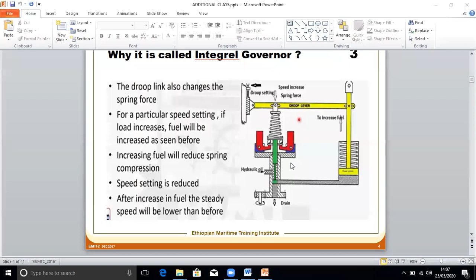You must understand why, when you increase the load, the speed reduces. This is because of this: the load current increases, and when the load current increases, the armature current will increase. So there is too much magnetic flux. The armature also produces a magnetic effect which will try to pull the rotor back. When the rotor is pulled back, the prime mover speed is dropped, and that is sensed by the governor and it gives more fuel. Okay, this is why fuel increases with increase in the load.